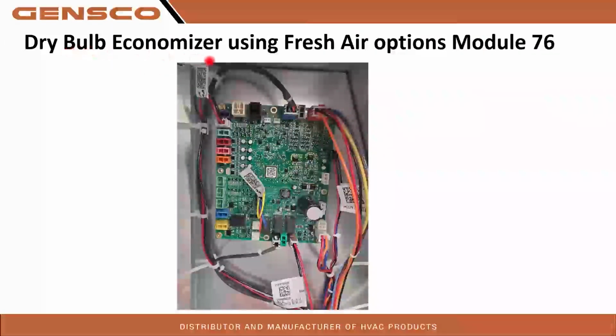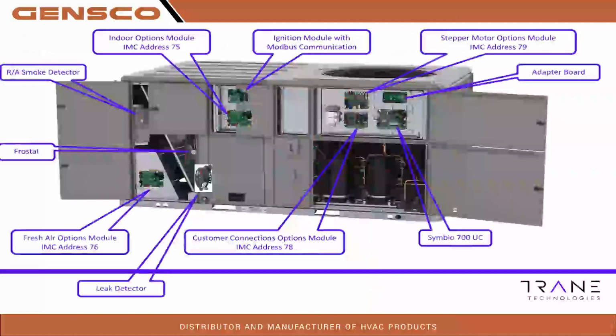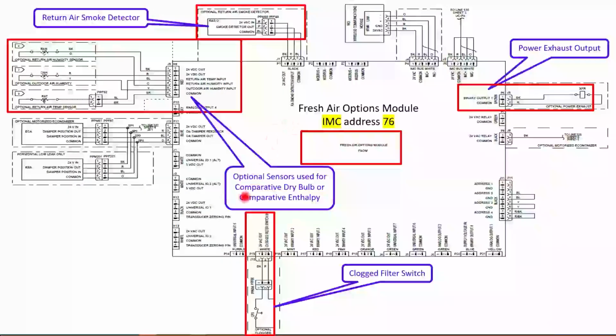So here's the dry bulb economizer using fresh air options module address 76. So again, here's those, it looks like where you plug in the heat strips, right? So it looks about the same. Here's our IMC connections. We are fresh air options module for the economizer right here. Optional sensors used for comparative dry bulb or comparative enthalpy are all going to land. Here's our return air smoke detector. So our return air smoke detector lands on the fresh air options module.